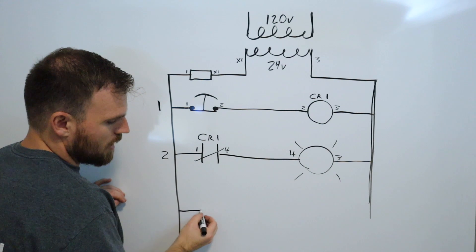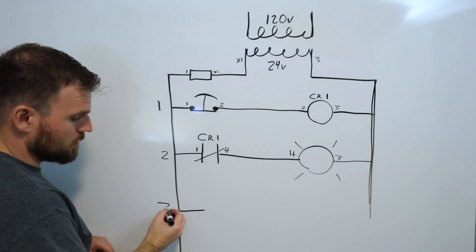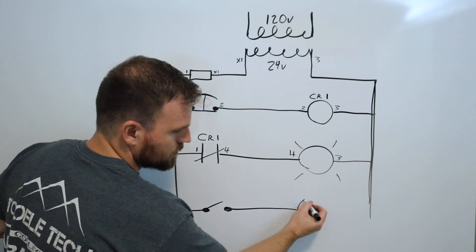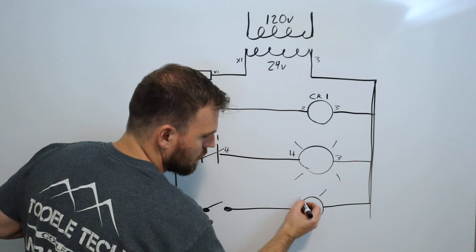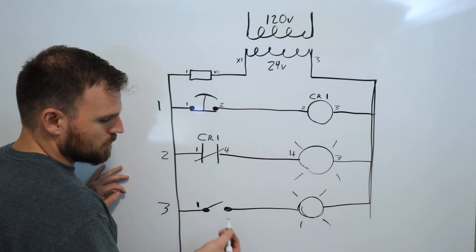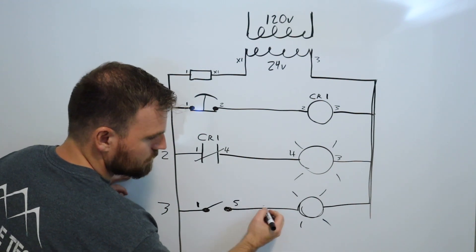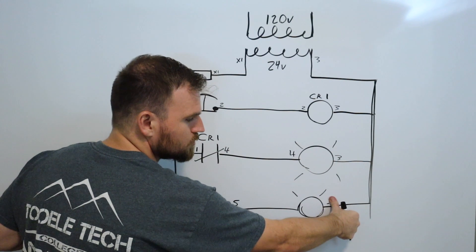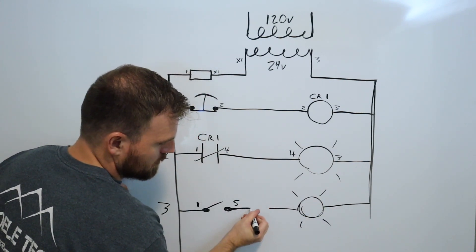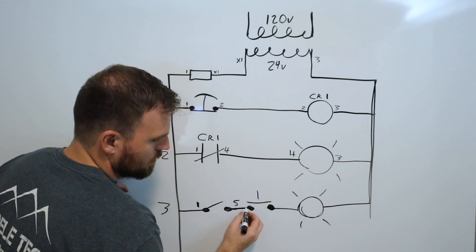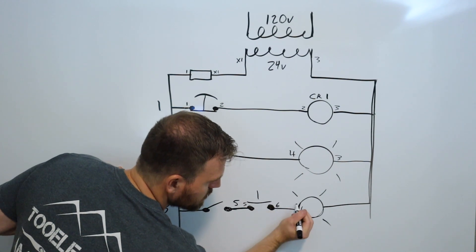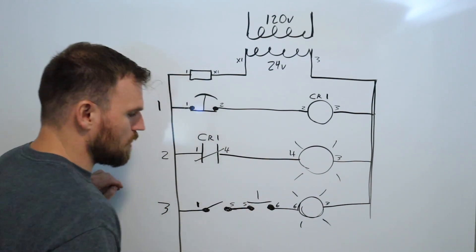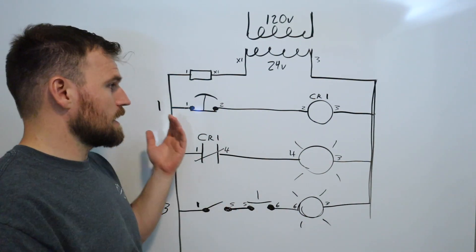Rung three can have another push button going to another light. Wire one comes in, passes through the push button and becomes wire five, then connects to the light and returns as wire three. If you add a second switch for an AND circuit in that same rung, wire five enters the second switch and exits as wire six, then connects to the output and returns as wire three. Multiple components just mean more wire numbers.